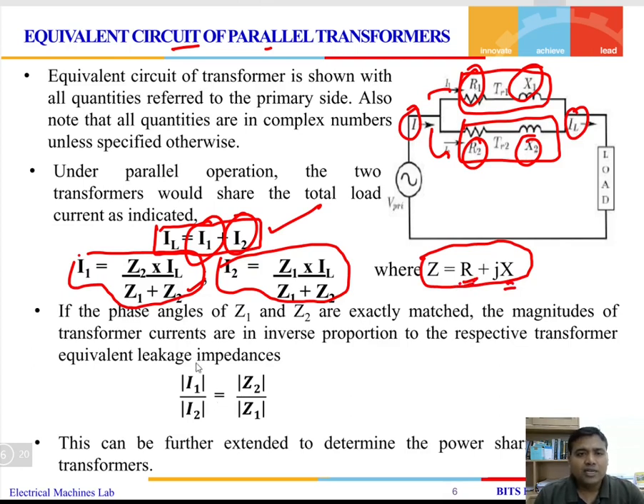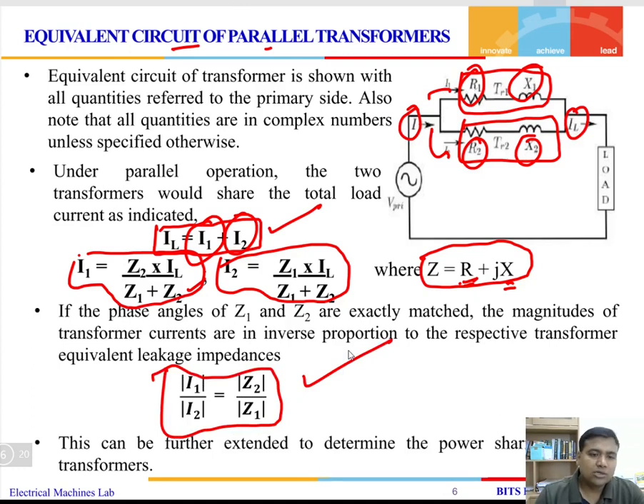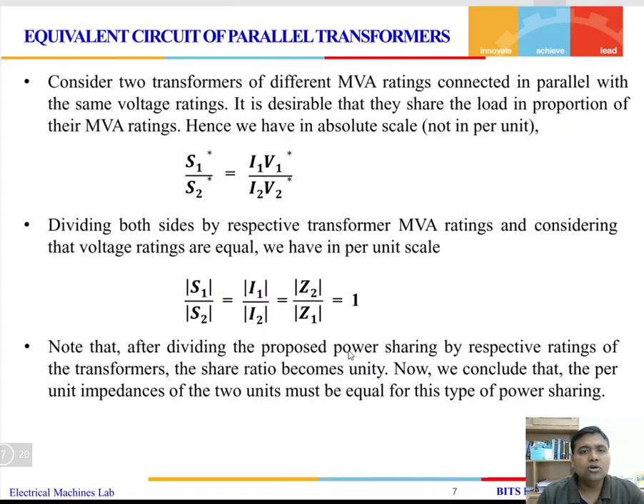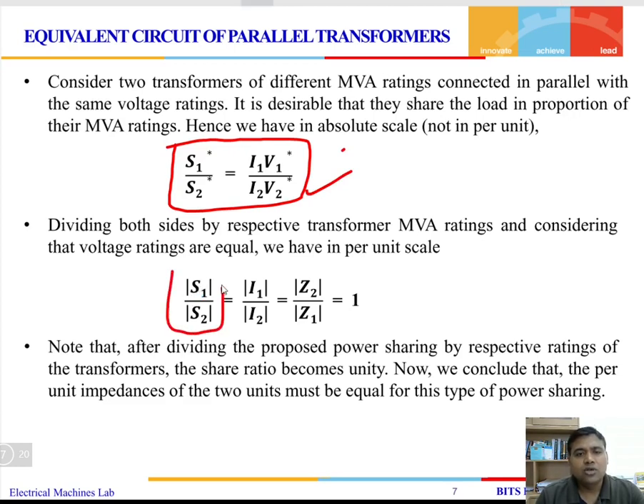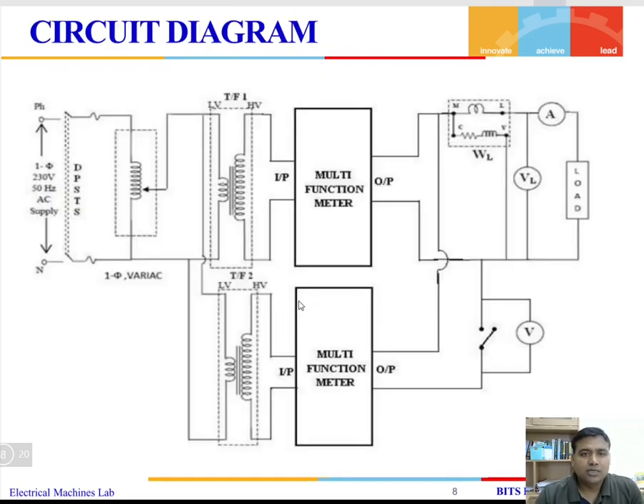Now, to meet the prerequisite, I1 by I2 will be equal to Z2 by Z1. This prerequisite has to be maintained so that load sharing can be done. Also, the complex power of the two transformers, S1 by S2, will be equal to I1 V1 conjugate by I2 V2 conjugate. So if we divide the complex power S1 by S2, we get the magnitude of the reciprocal current ratio I1 by I2 times the impedance ratio Z2 by Z1, which should be equal to 1. These conditions need to be maintained so that efficient parallel operation of the transformers can be done.